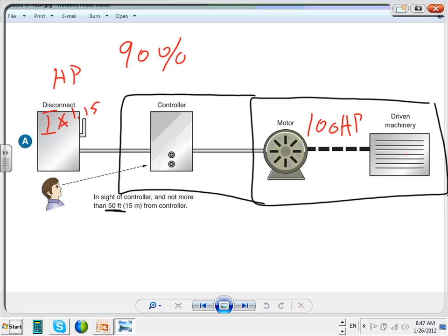It's not supposed to, but if somebody comes accidentally or intentionally when this machine is running, you're not supposed to open this when it's running. If somebody, for whatever reason, decides to open it while the machine is running, this is not going to blow off the wall. That's what the horsepower rating is. Otherwise, if it's not horsepower rated, somebody could come here and turn it, having no idea what a disconnect is, thinking it's a controller. The whole thing is going to blow off the wall if it's not horsepower rated. Does that make sense? The gravity of a horsepower rating? Horsepower is power, obviously.